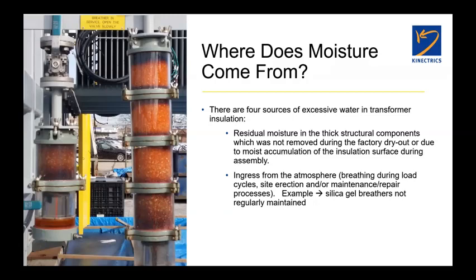It's possible for moisture from the atmosphere to get into the transformer, even though we might be extremely careful, purging with dry nitrogen or whatever. So those operations are an avenue for moisture ingress. Leaks are a third method. And leaking gaskets, rips, pinholes, tears in airbags or air bladders in conservator tanks, if a conservator is equipped with one of those. Weld pinholes.